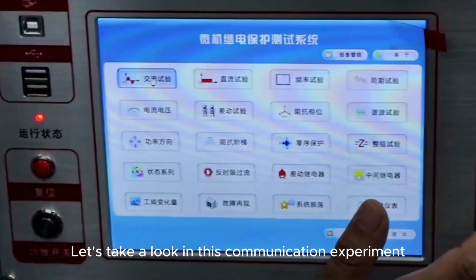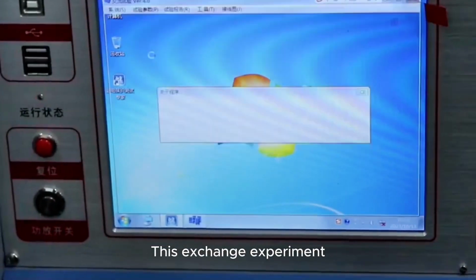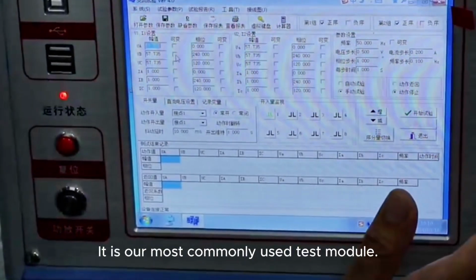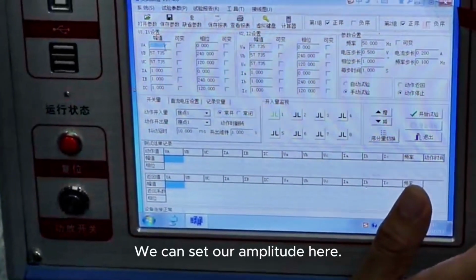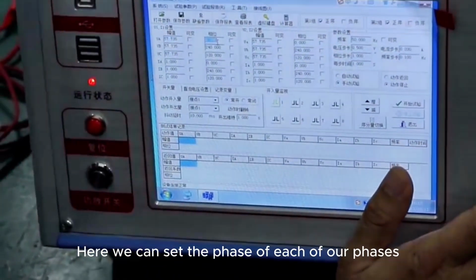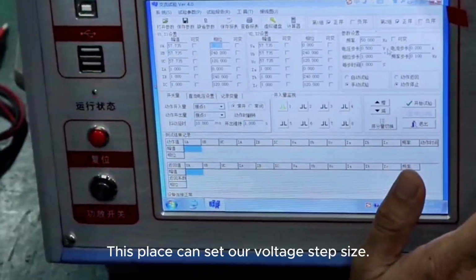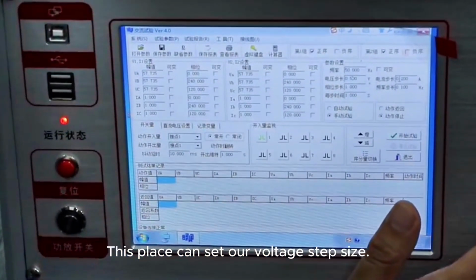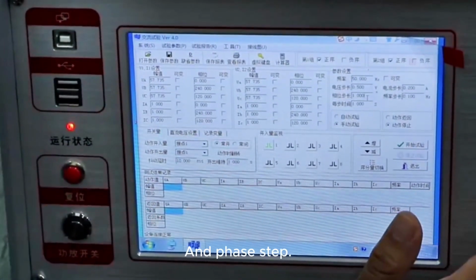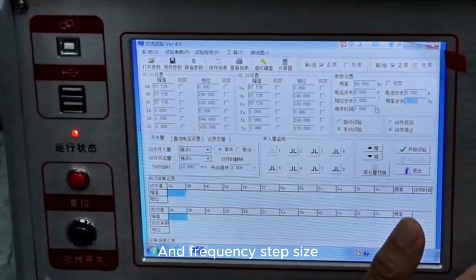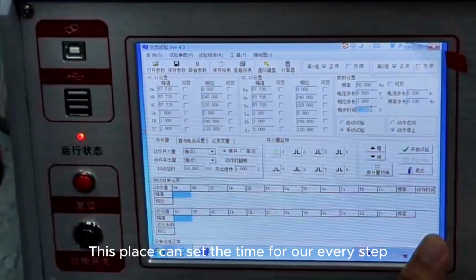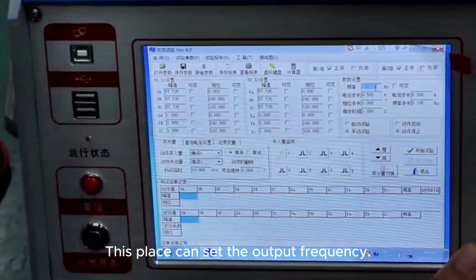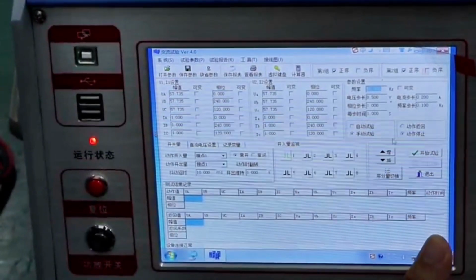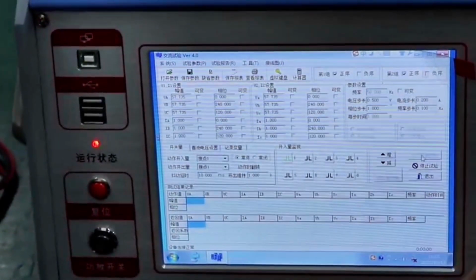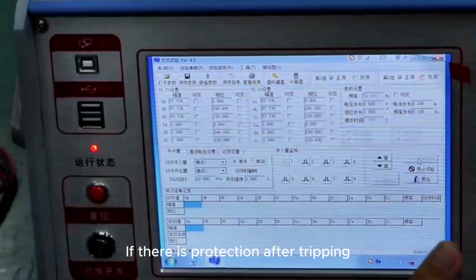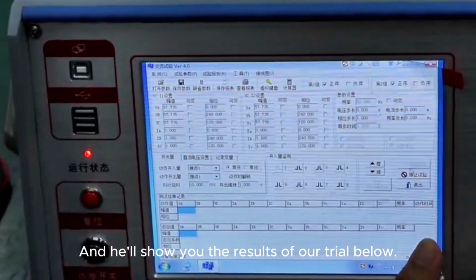Let's take a look at this AC experiment. This AC experiment is our most commonly used test module. We can set our amplitude here. Here we can set the phase of each of our phases. This place can set our voltage step size, current step, phase step, and frequency step size. This place can set the time for every step. This place can set the output frequency. So we start experimenting. If there is a protection trip, it will show you the results of our trial below.